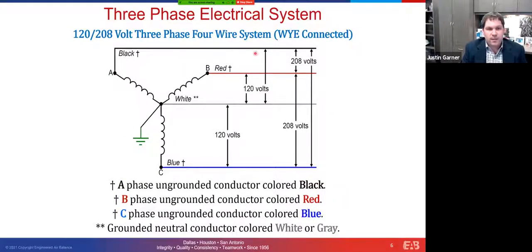This is the step down in most commercial facilities. And when I say step down, I'll explain that in the next slide. But this is when you typically come into a facility at 480/277 volts. And that's what would feed most of the larger equipment, lighting, things like that. And then you're going to have transformers that step that voltage down to a 208/120 system to feed smaller equipment and mostly your plug loads and things like that within the facility and maybe a myriad of other things. But normally this is just plug loads and maybe some smaller HVAC equipment if you have some single phase fans, or things of that nature, you may have that fed off of here.